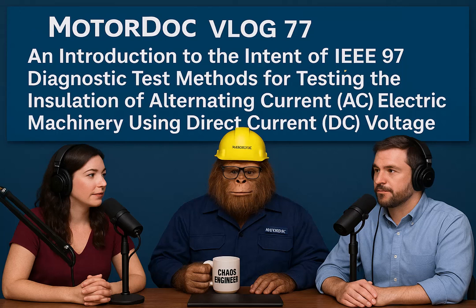And moisture. We know that's a classic insulation killer. It is. Moisture or water absorption dramatically increases the conduction current. It could be simple surface moisture, or it could be absorbed deeper into the bulk material, especially with older, more hygroscopic materials like asphalt or some polyesters. Right. Stuff that likes to soak up water. Exactly. The guide notes this causes the current to increase in a nonlinear way with voltage. They even mention something called the electroendosmosis effect. Electroendosmosis. What's that? It's where the electric field itself actually causes moisture within the insulation to physically migrate, to move around, which can sometimes lead to different resistance readings depending on whether you're testing with positive or negative DC voltage.